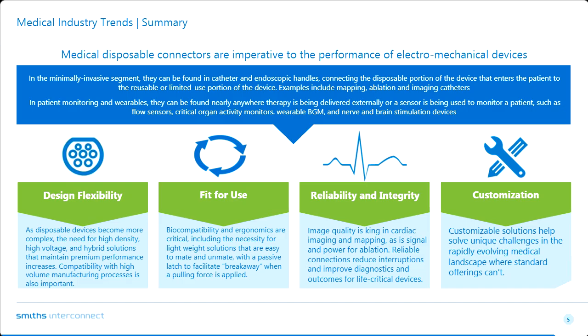When we look at some of the industry trends and what that means for how we design, that's what we'll cover here. So medical disposable connectors are imperative to the performance of electromechanical devices. Electromechanical meaning anything that you're using to deliver energy or a signal or power of some kind. So all of the connectors we make are, let's say, electrical in nature. In the minimally invasive segment, typically you find disposables in catheter and endoscope handles, which connect the disposable side of the device, which is typically everything from where the doctor is holding a handle and delivering care to the patient, all the way to the very tip that is touching the patient, whether it's inside the body or outside the body.